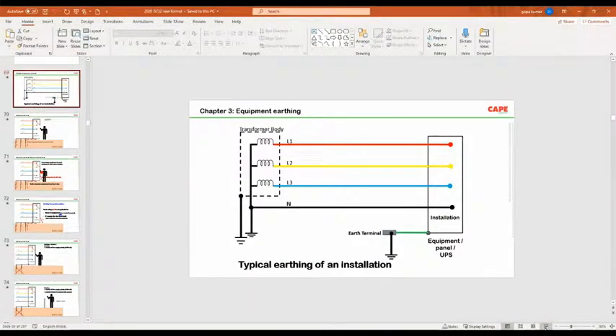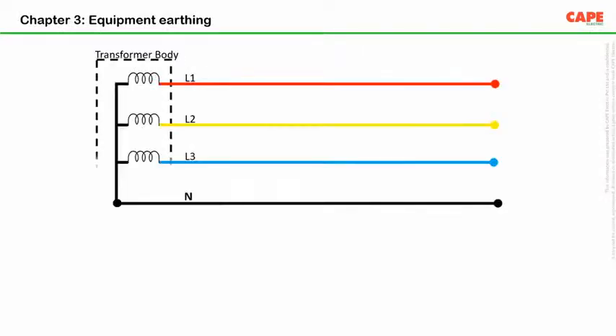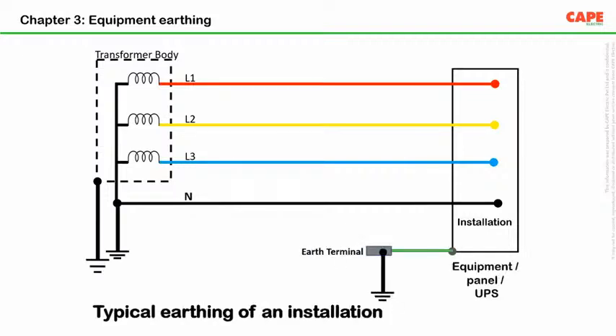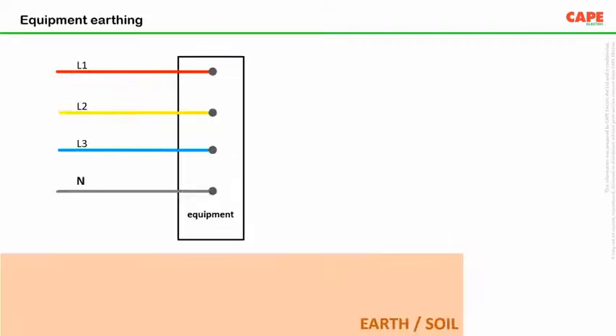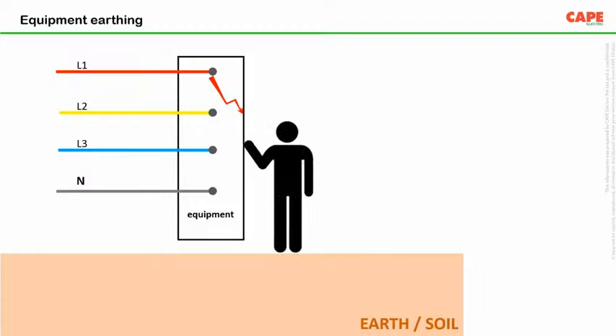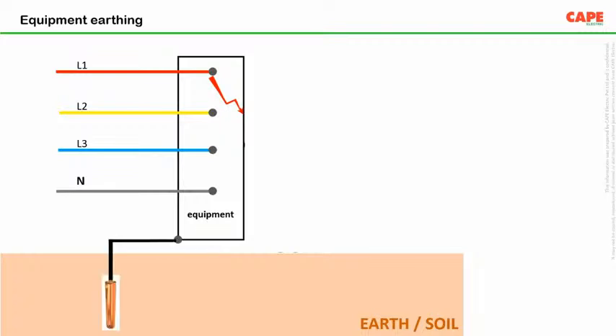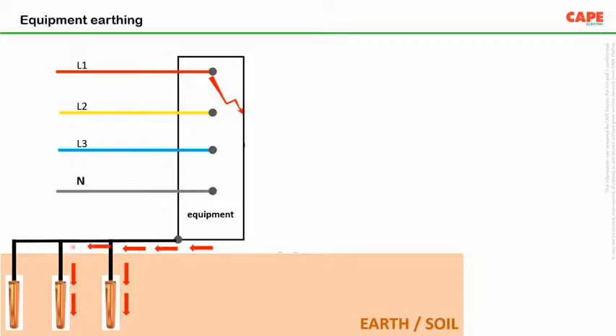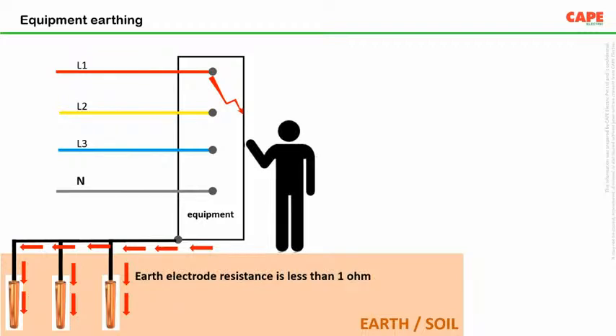So imagine, now we will have the full screen. Imagine there is a transformer, there is an equipment, and generally what we do is the transformer neutral and body are separately earthed, and the equipment is separately earthed. And then on the equipment, only on the equipment, what we generally think is, okay, there is a fault, what do we do? A person touching the equipment will get a shock. So people say earth it. And then generally in industry, what we do is buy 2-3 earth electrodes and connect the equipment to the earth pit, and then think that the fault current goes to earth. As a result, somebody touching will not get a shock. Even people say that the person will not get a shock.